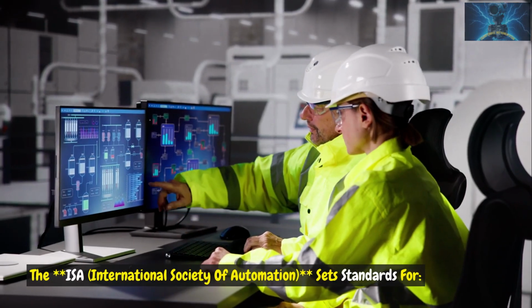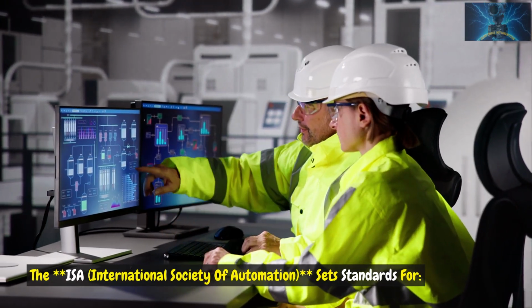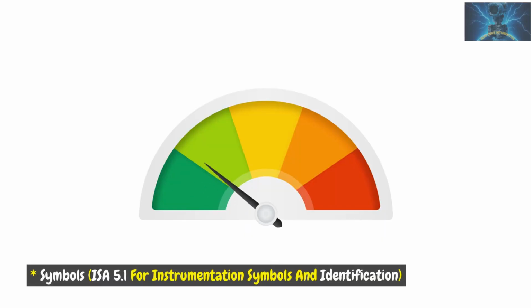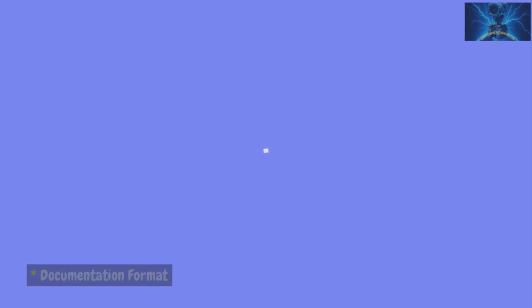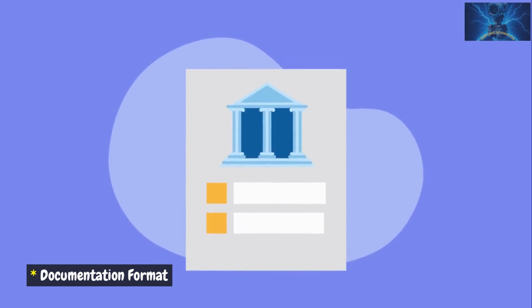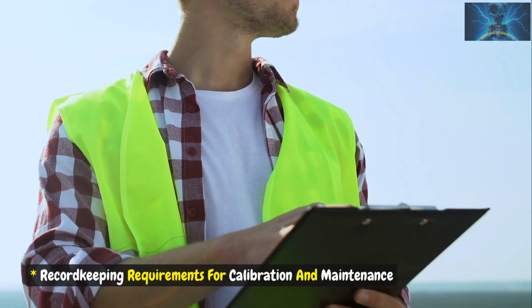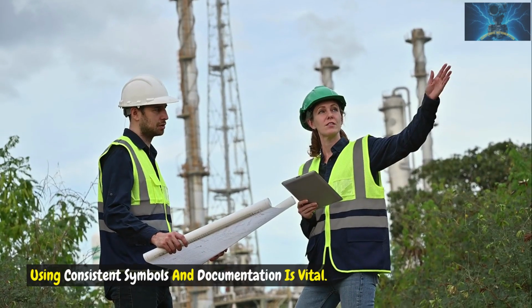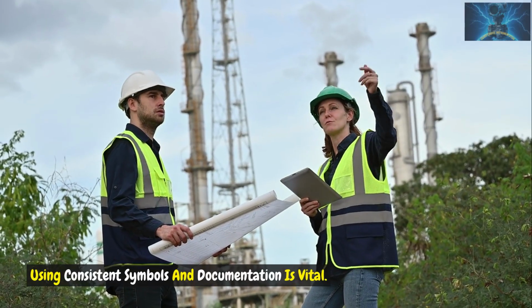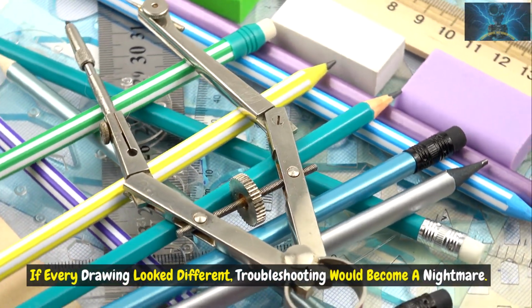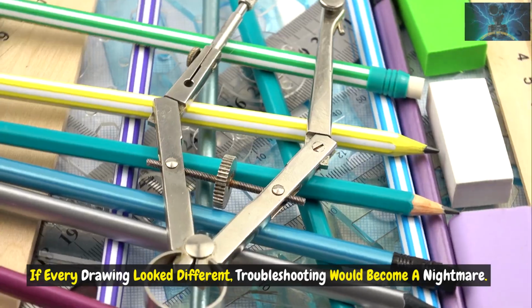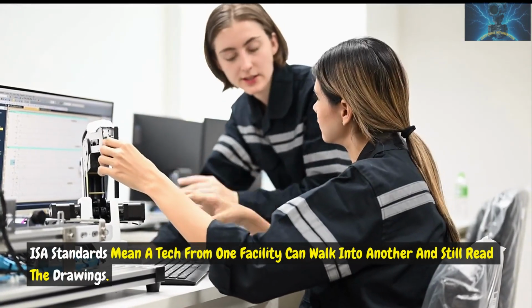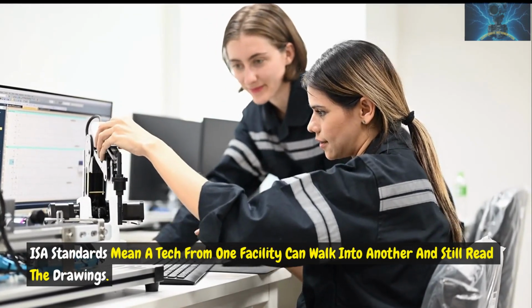There are also standards that keep everything consistent. The ISA, International Society of Automation, sets standards for symbols, such as ISA 5.1 for instrumentation symbols and identification, as well as documentation format and record-keeping requirements for calibration and maintenance. Using consistent symbols and documentation is vital. If every drawing looked different, troubleshooting would become a nightmare. ISA standards mean a tech from one facility can walk into another and still read the drawings.